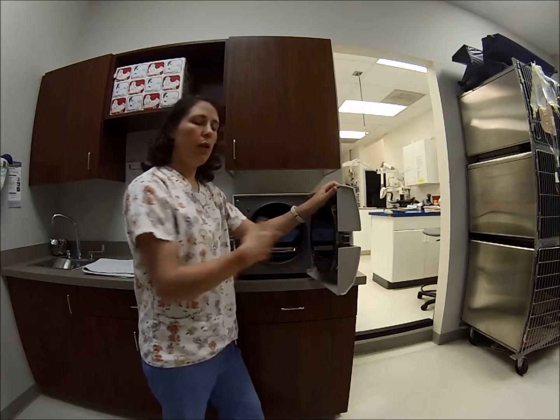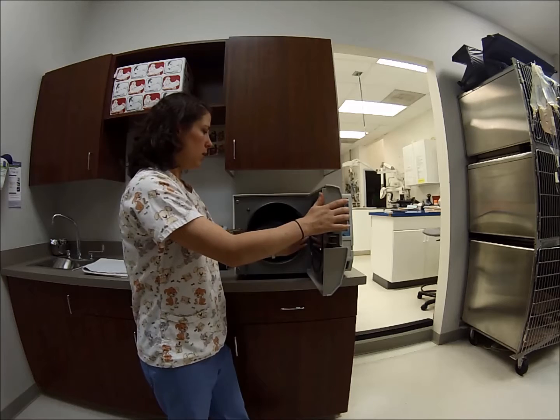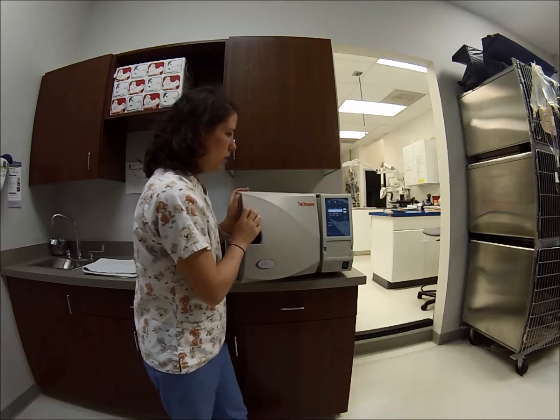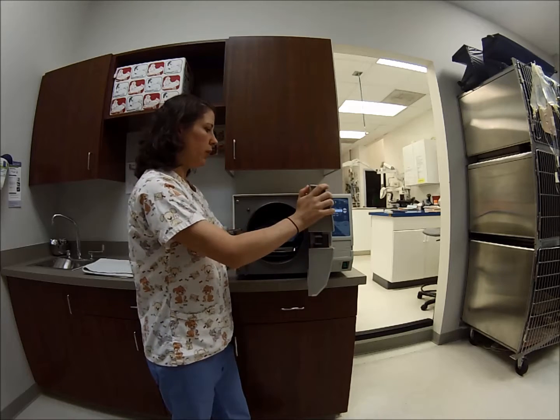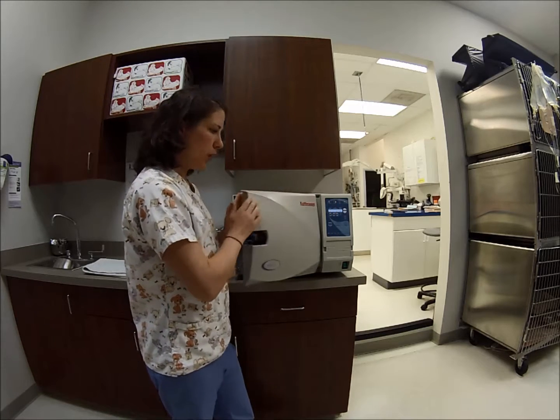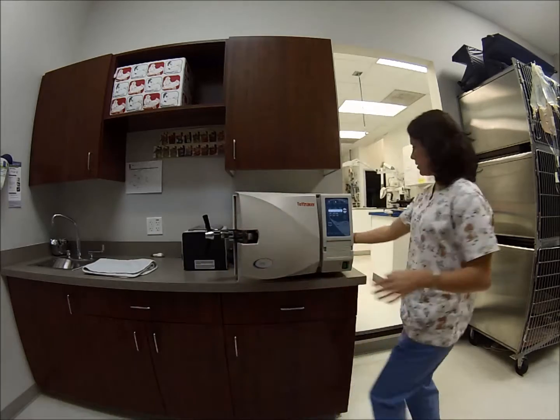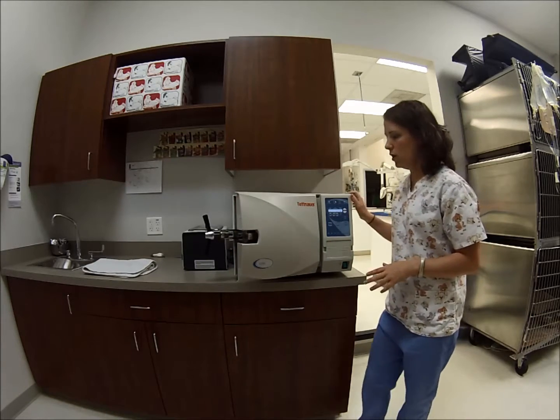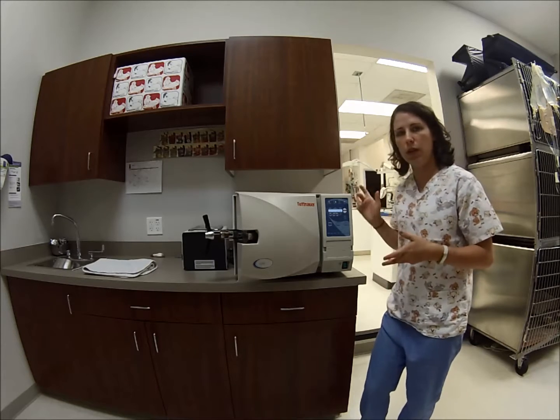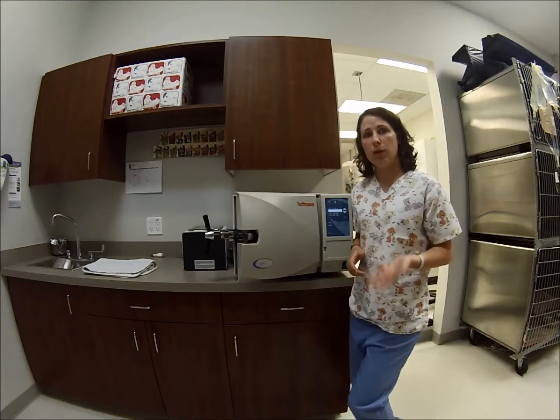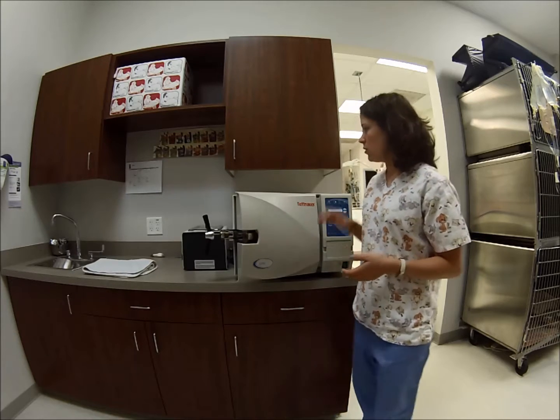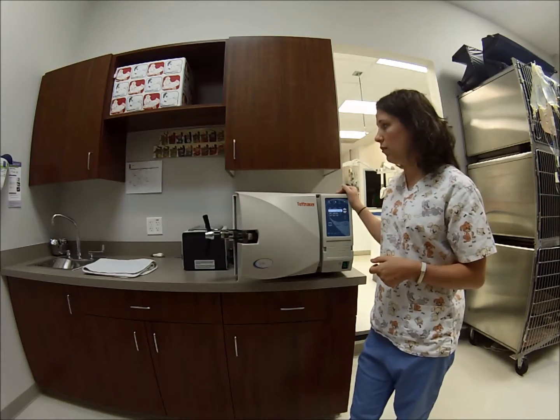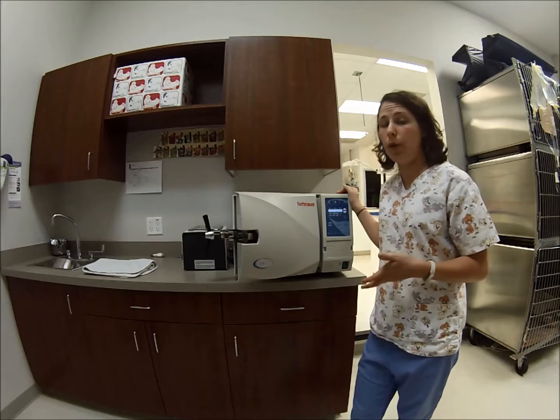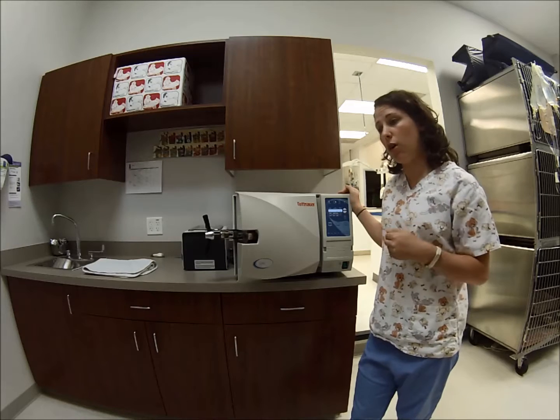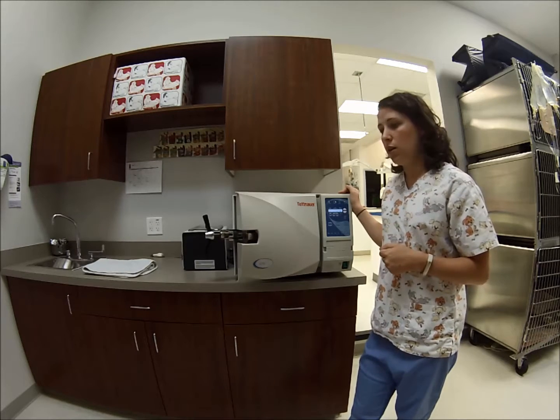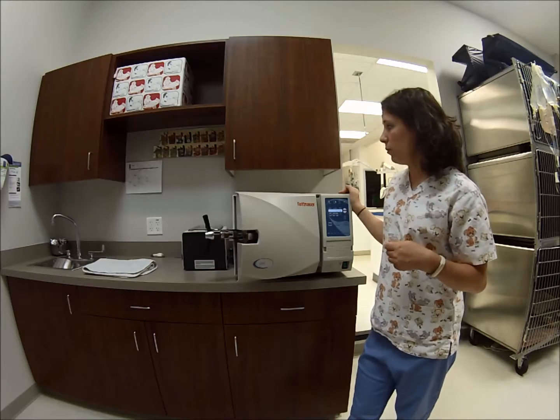Another thing we'll want to check about once a month is the seal on the gasket. Just check for any damages. About once a year, we'll actually replace this gasket so we have a nice seal, as well as the air filter, which is on this side here, just to make sure there's no spores building up, which is another thing that we do, is bactericidal spore testing. So it's important to keep up with maintenance on your autoclave, because you don't want to have any problems with sterilization. We have a binder log that we fill out, like I said, every week to every month, and then once a year we perform those tasks.